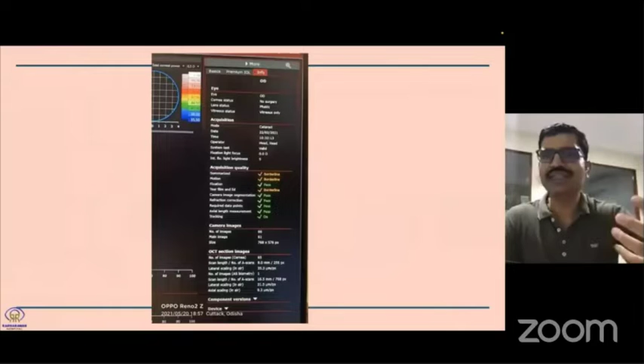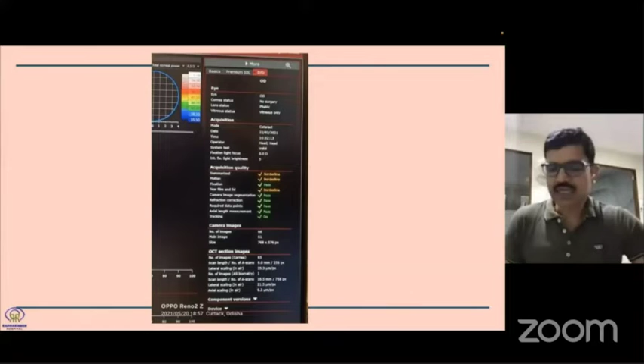The earlier machines just had the standard deviation as the only reliability indicator. This is one other modern day machine which also utilizes ray tracing technology along with swept source OCT, where a host of acquisition quality indicators has been represented. And you can see, fourth from top, the tear film and the lid integrity are also shown by the machine. It does not calculate or show the tear film integrity to you, but if the machine does not find it trustworthy, it will always give you a signal whether it's acceptable or not.